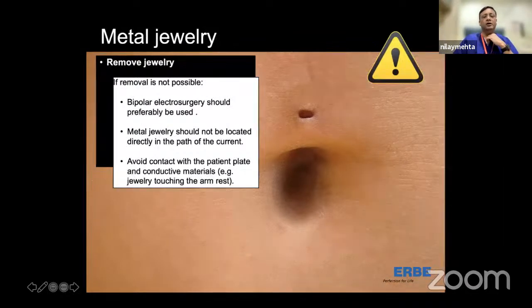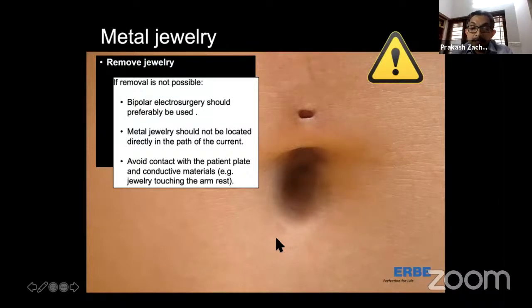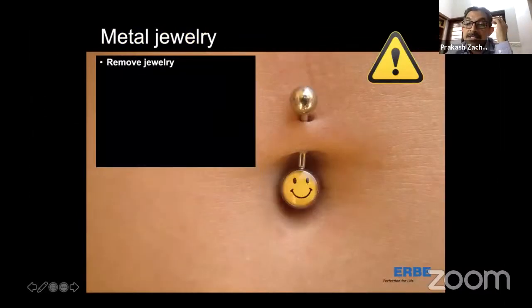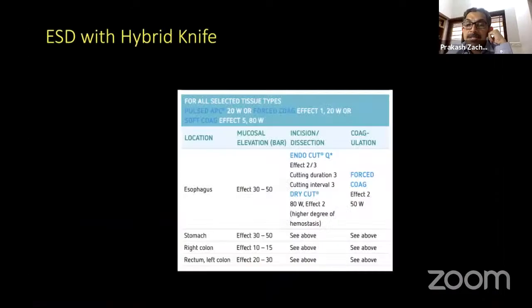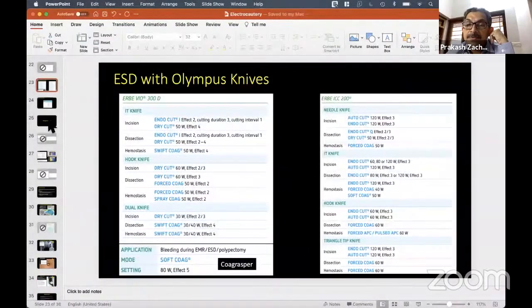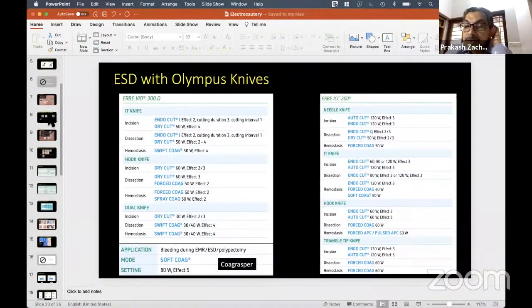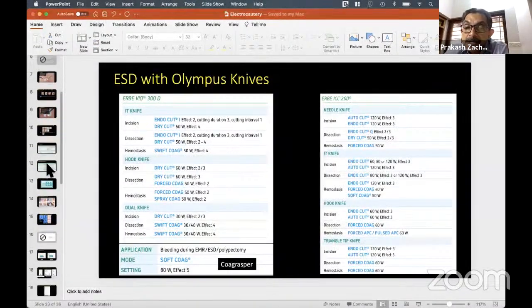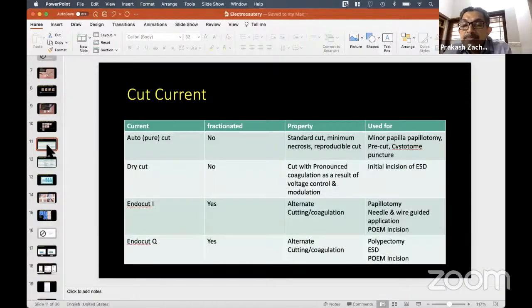Yeah. So the thing is that the traditional electrosurgical generators provide only constant wattage, and that will not be enough for procedures like ESDs and POEM. For that, a high performance computerized ESG is required, which provides modulated current options.